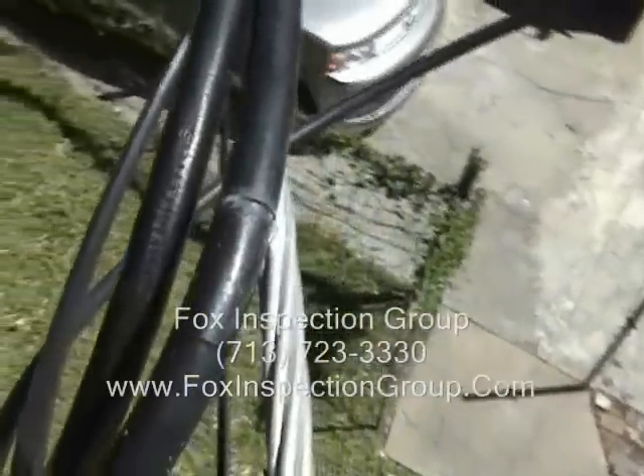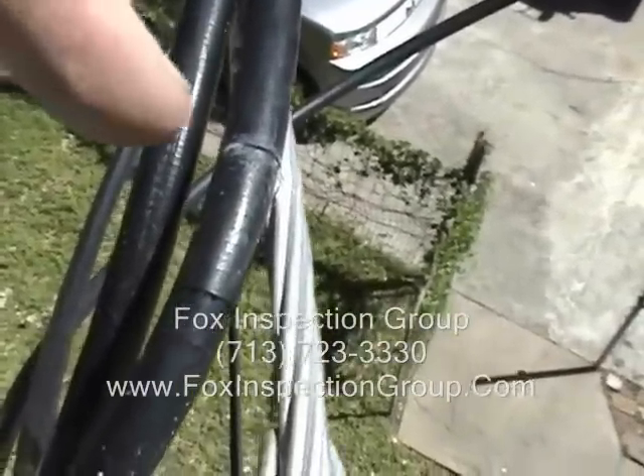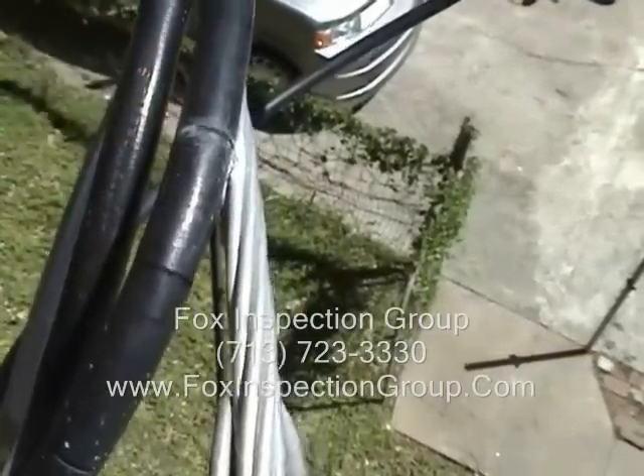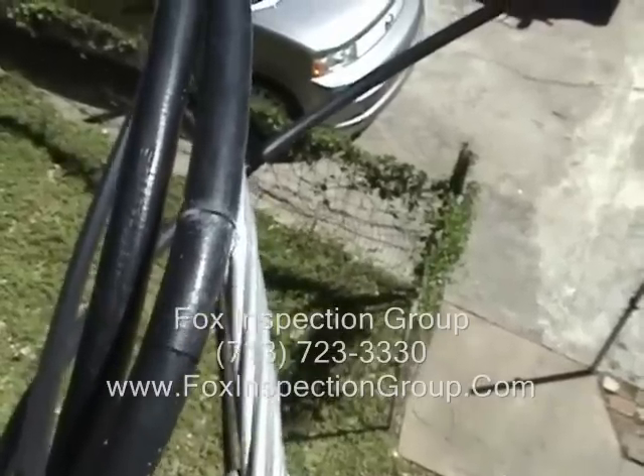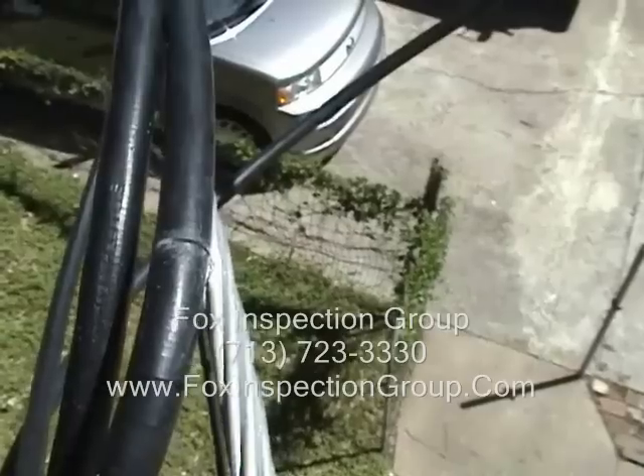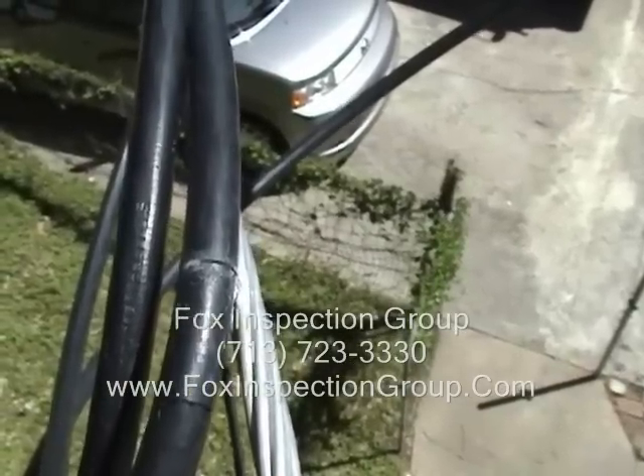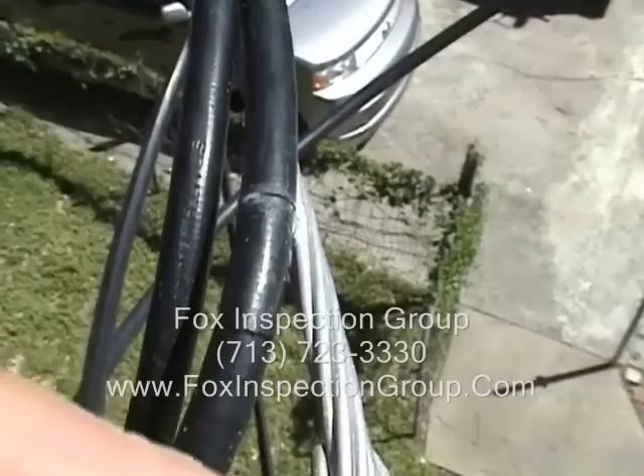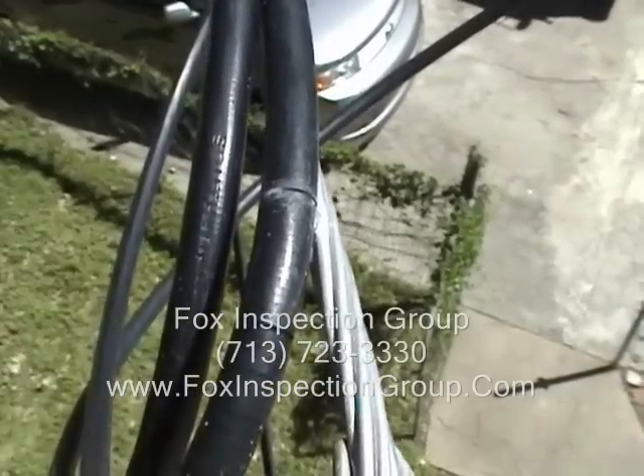Try to get different angles — there you go, that's a good crack. Good angle on it, right there. The telltale sign will be some white effervescence from the arcing. We've even got photos of it where it will actually burn through some of the neutral wire.